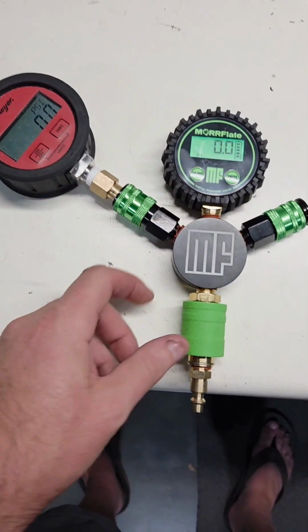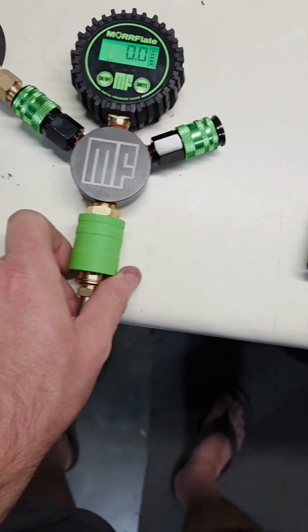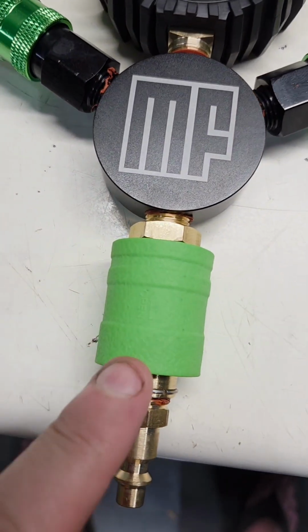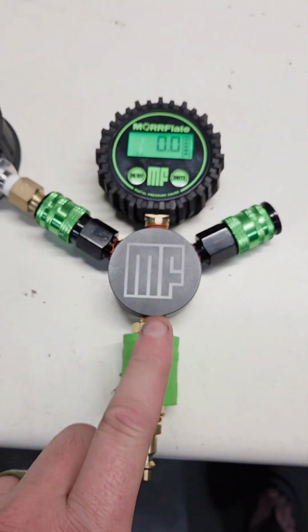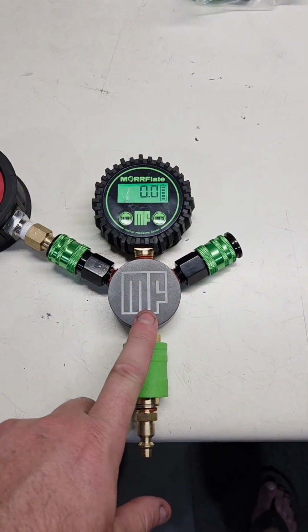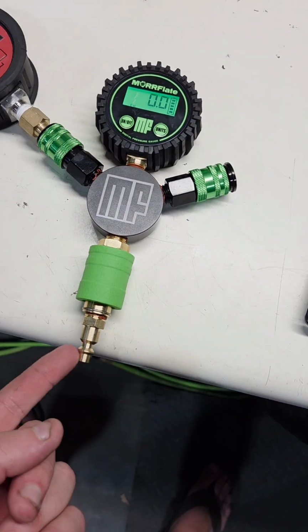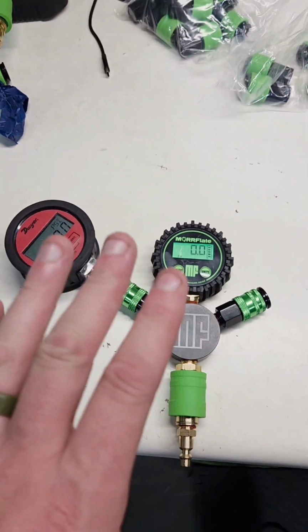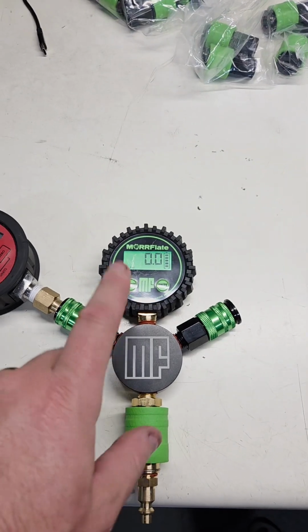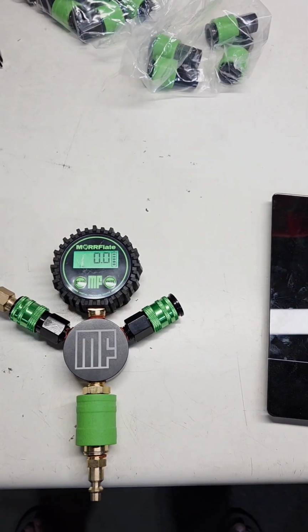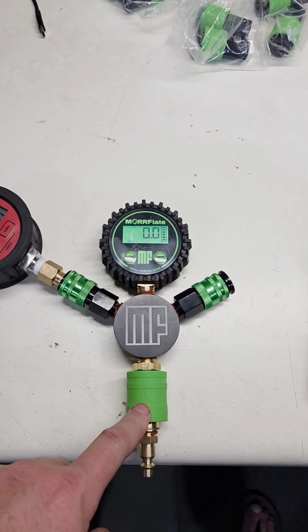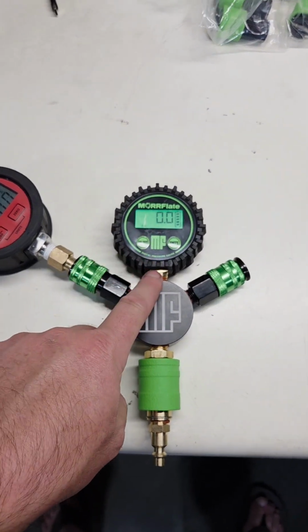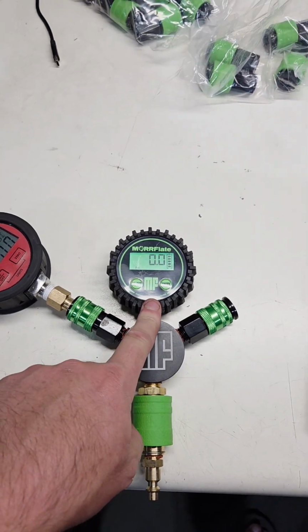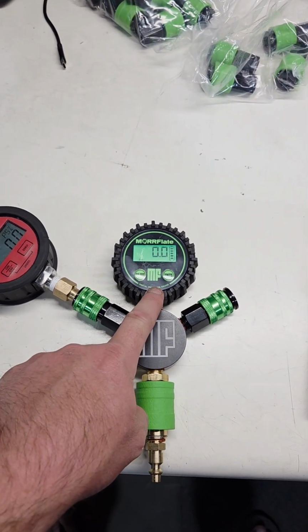Just like that. Ensure that your valve is open, so it's set to atmospheric pressure. You see here, we have a little open tag here. So open is up. With the valve open, that means everything that's coming in this nozzle is set to atmospheric pressure. And then take out the batteries on the back of your gauge, put them back in with this valve open to atmosphere, and that will force a recalibration of your digital gauge and digital sensors.